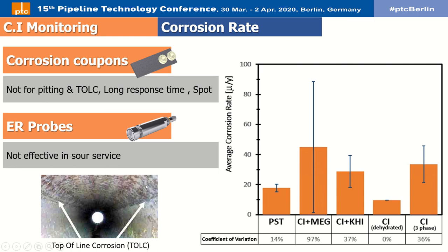In one of the lines, after only two years of operation, a 3 mm localized corrosion was detected due to stratified flow and the inability of corrosion inhibitor diffusion in the gas phase. Severe localized corrosion was also detected on similar dead-leg zones where water-saturated gas is trapped, analogous to top-of-line corrosion. Unfortunately, the only plausible technique to detect metal loss due to top-of-line corrosion is ILI — in-line inspection — which is not frequent enough to capture the threat at earlier stages.